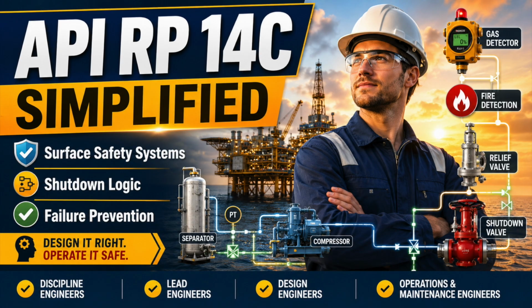A pressure vessel can experience overpressure, underpressure, overflow, gas blow-by, leakage, and excessive temperature. A flow line can experience overpressure and leakage. A pump can experience blocked discharge overpressure, leakage, and reverse flow. A compressor can experience suction or discharge overpressure, low pressure, high discharge temperature, leakage, gas accumulation, and backflow.